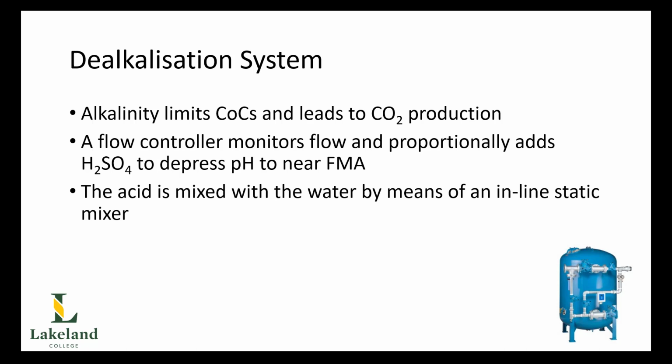Now, the way in which that is done is using a dealkalization system or a dealkaliser. And the basic way in which this works is that we have a flow controller that will monitor our feed water flow and proportionally add in sulfuric acid to depress the pH to near free mineral acidity.